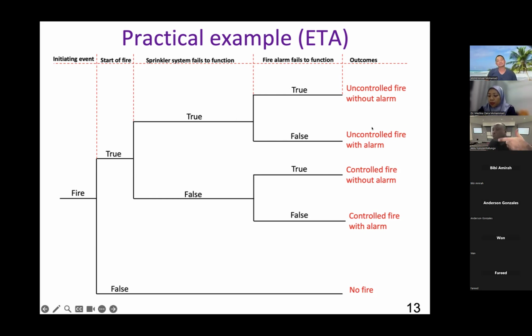Okay? So there was a fire. The fire was not controlled because there was no sprinkler, but at least people were informed by the alarm. Now, the worst scenario is there was a fire, the sprinkler system failed, which means there was no control for the fire, and the alarm system did not work also, which means people were not informed. So you had an uncontrolled fire without alarm. Does this make sense to you?